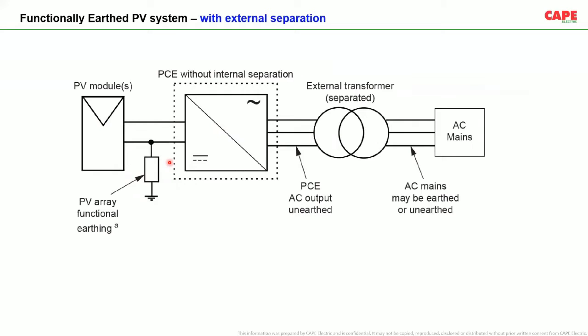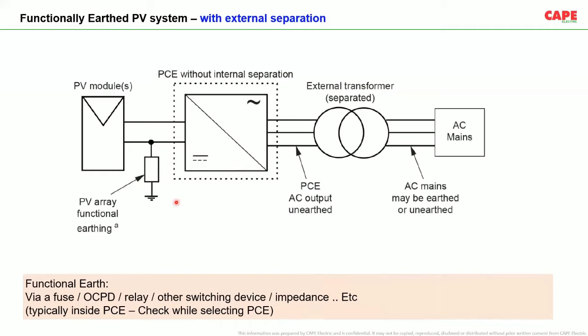Functionally earthed means this earthing has a certain purpose. Number one, this earthing will create a stable voltage on that particular line from the secondary side of the transformer up to the last PV module. The voltage is stable. And very important, the functional earthing is always made with a kind of device. For example, in this circuit, the PV array functional earthing, there can be a fuse, a protective device, a relay, some kind of switching device, or an impedance. The idea is, let me draw it one moment.